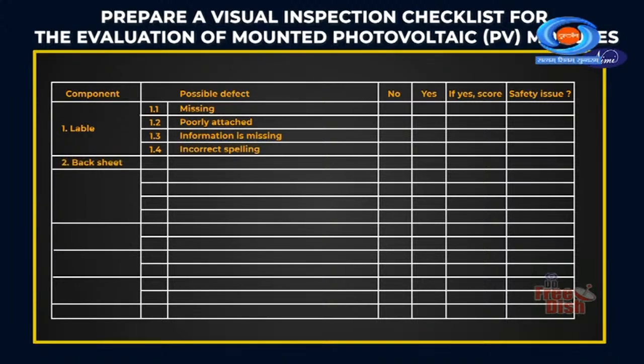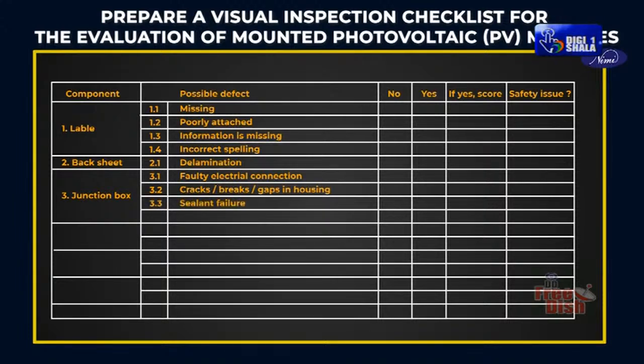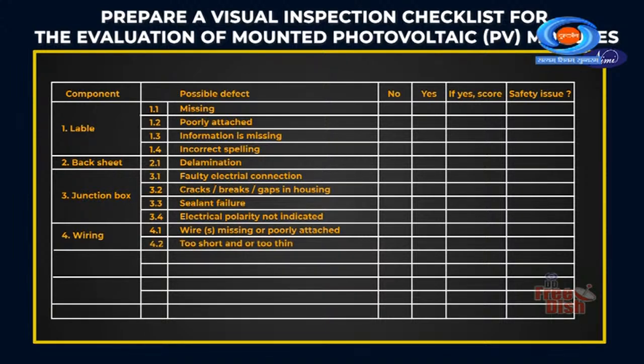Component, backsheet, possible defect: delamination. Component, junction box, possible defect: faulty electrical connection, cracks or breaks or gaps in housing, sealant failure, electrical polarity not indicated. Component, wiring, possible defect: wire or wires missing or poorly attached, too short and or too thin. Component, frame, possible defect: damaged, adhesive or sealant failure. Component, front glass, possible defect: cracking, scratches.